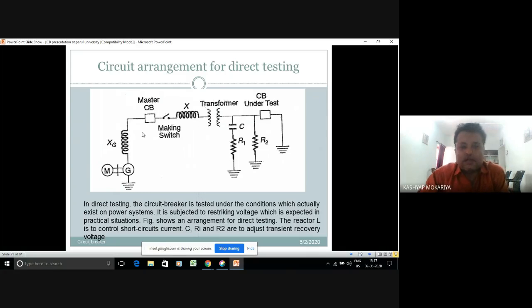Therefore the master circuit breaker, the calibrated breaker, in every condition while testing the breaker in your manufacturer premises here, it should operate. Here it is written that the reactor L is for controlling the short circuit current, and this is that reactor here, L or X. C, R1 and R2 are to adjust the transient recovery voltage. You can adjust your transient recovery voltage with the variable settings here, and obviously it is given in direct testing.